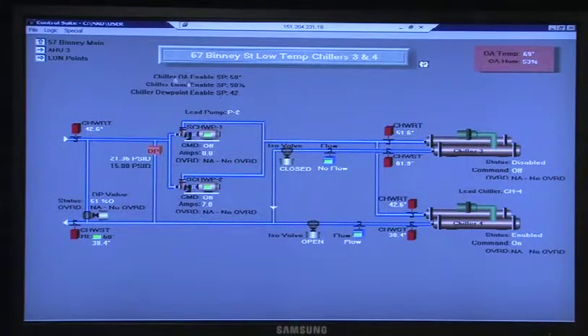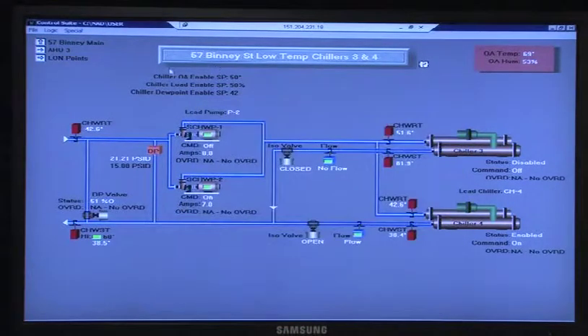A unique thing to this is, you see the things on the top of the screen there, that enables. It's either, if the outside air is above that outside air enable, it's going to enable the chiller, or if the dew point is above that 42, it will start it. So it's either or, it's going to start the chillers. The middle piece is going to come out. We ended up changing the lag chiller, starting a lag chiller based on enthalpy. So we're going to have an enthalpy set point in there that's going to end up changing.